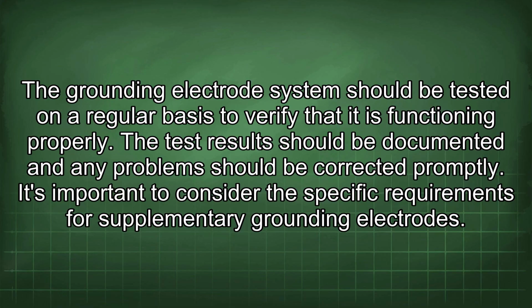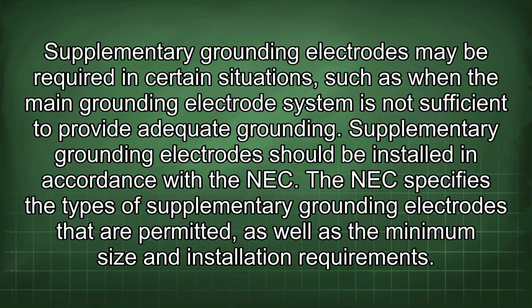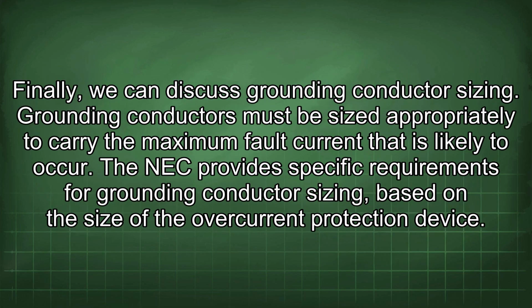It's important to consider the specific requirements for supplementary grounding electrodes. Supplementary grounding electrodes may be required in certain situations, such as when the main grounding electrode system is not sufficient to provide adequate grounding. Supplementary grounding electrodes should be installed in accordance with the NEC. The NEC specifies the types of supplementary grounding electrodes that are permitted, as well as the minimum size and installation requirements. Finally, we can discuss grounding conductor sizing.